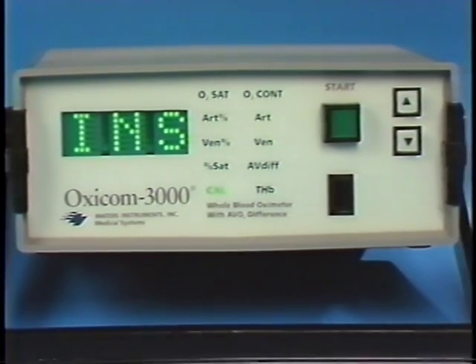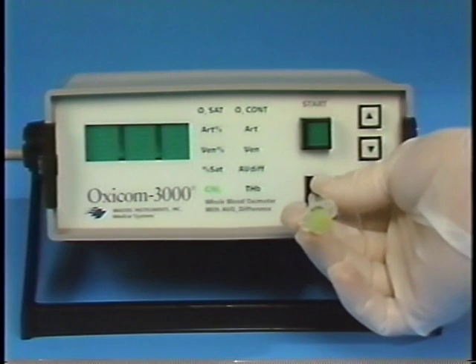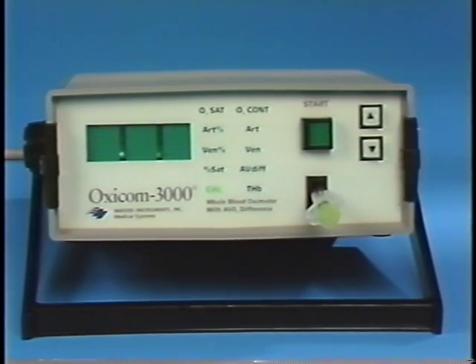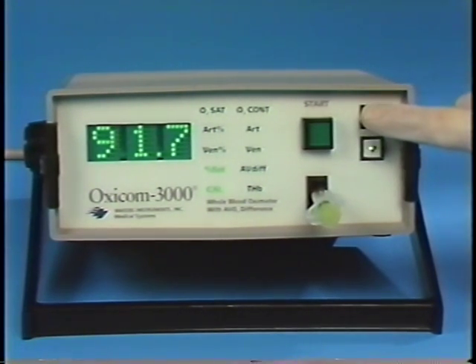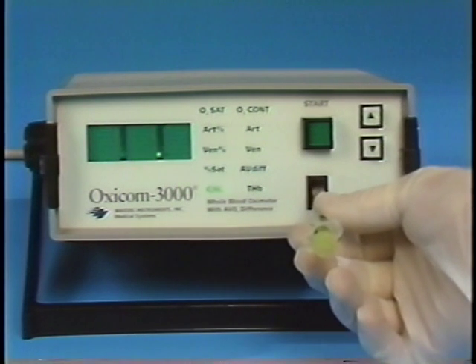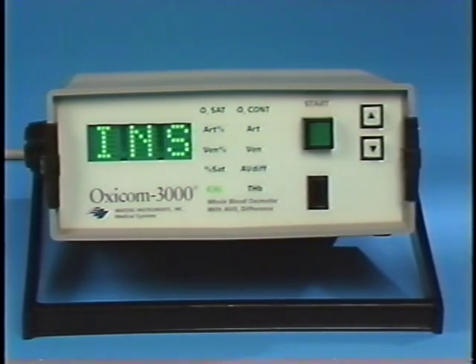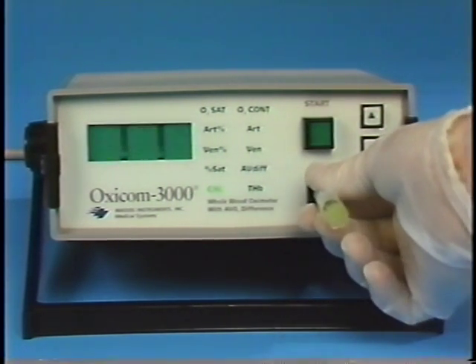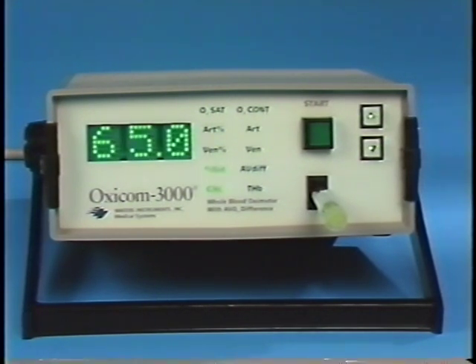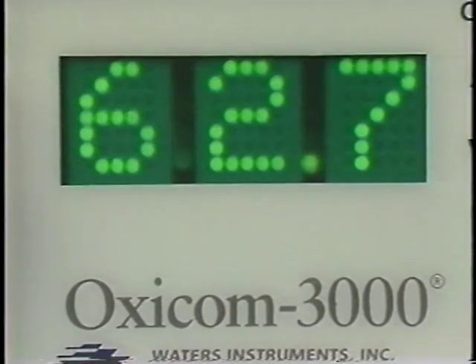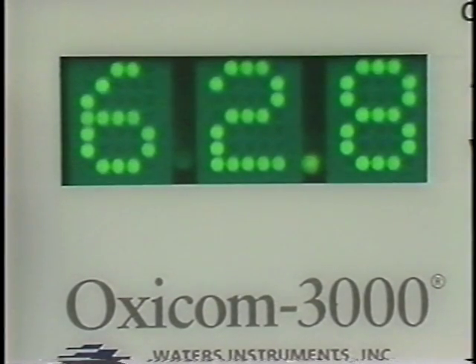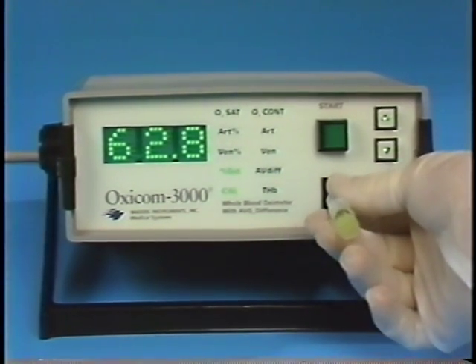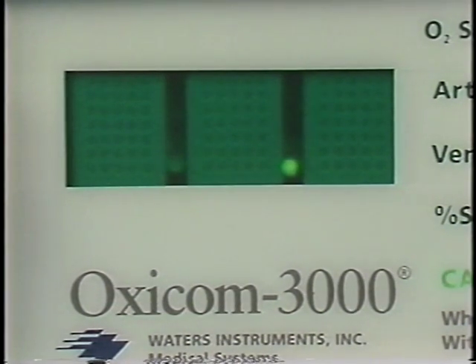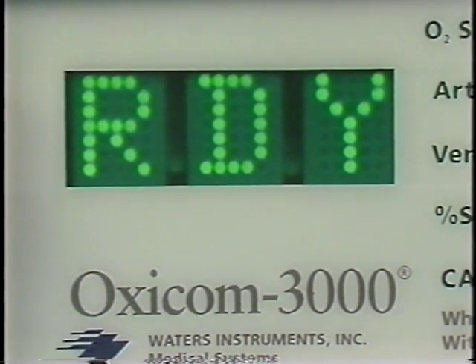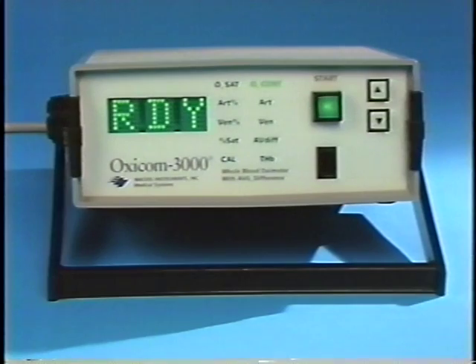Insert the arterial or high sample. Leaving the cuvette in the sample port, use either the up or down arrows to increase or decrease the displayed value to that of the sample value calculated on the co-oximeter, or in our example, 91.7%. After removing that cuvette, INS will appear again. Insert the second or lower sample. Again, we use the arrows to adjust until the sample value reads 62.8. Remove the second cuvette. The decimal points are flashing, indicating the oximeter is calibrating itself to the two samples. In less than 1 minute, it will display RDY and will be ready for your operation.